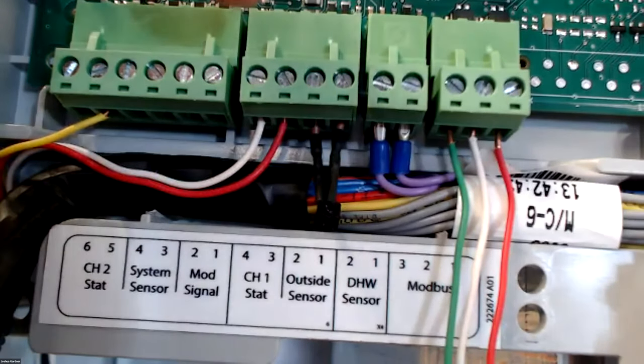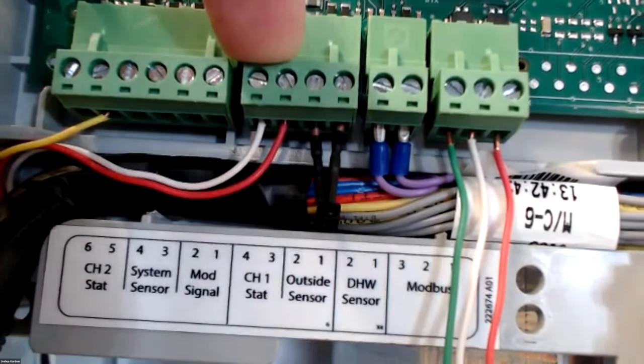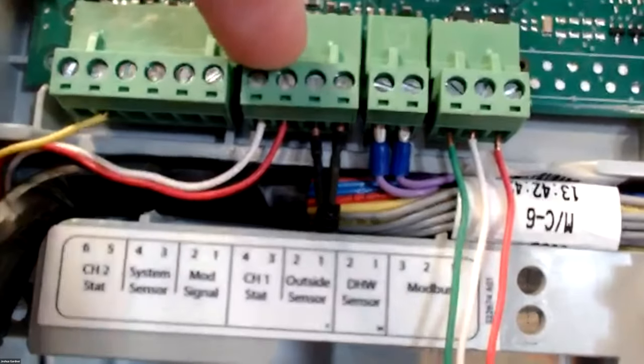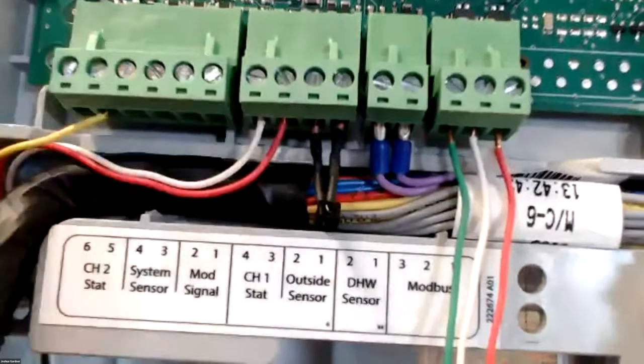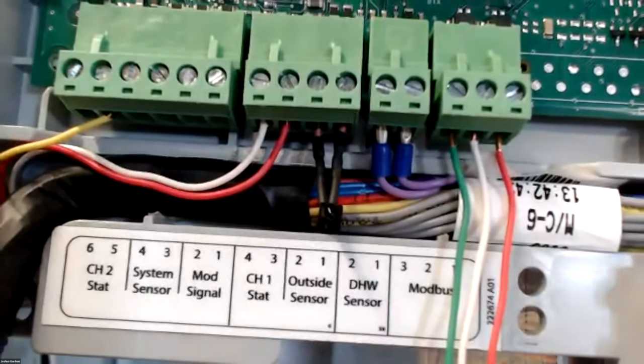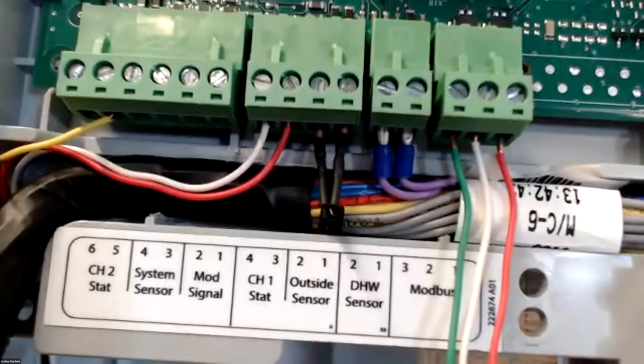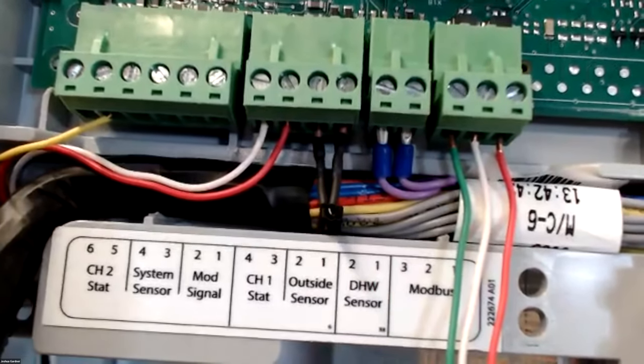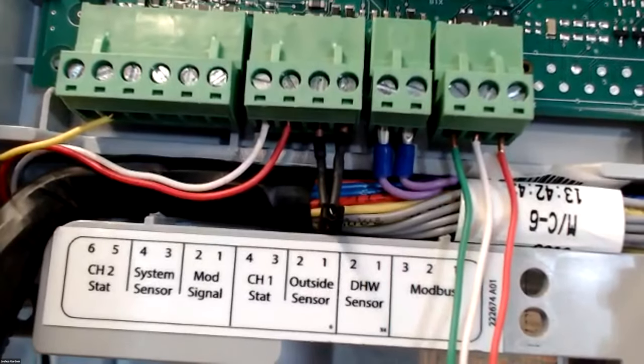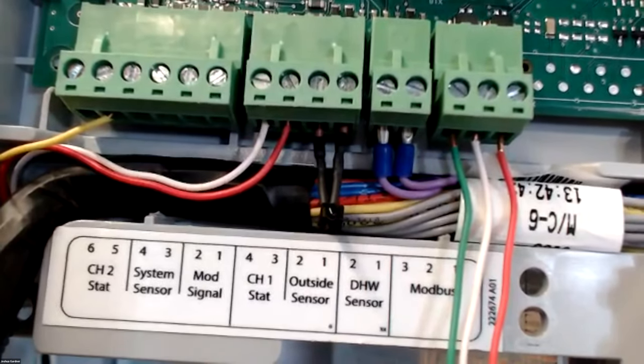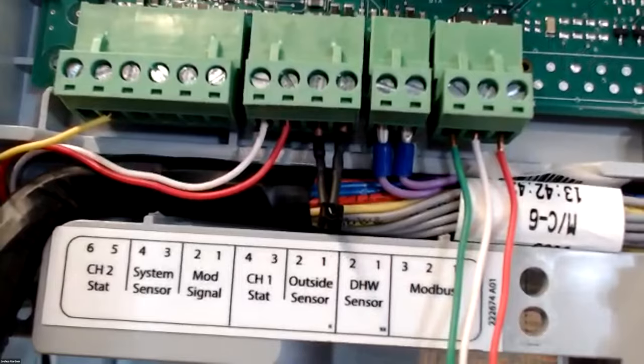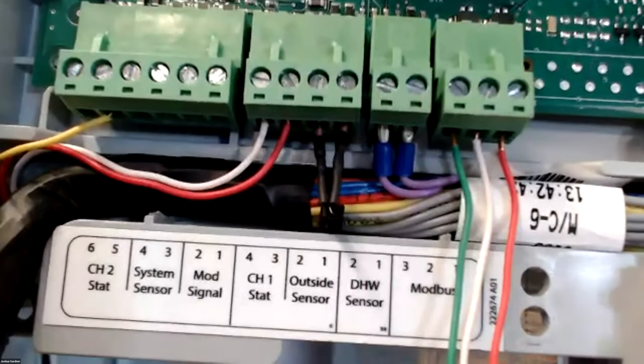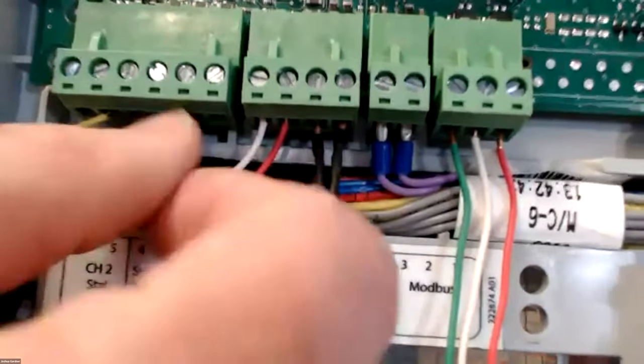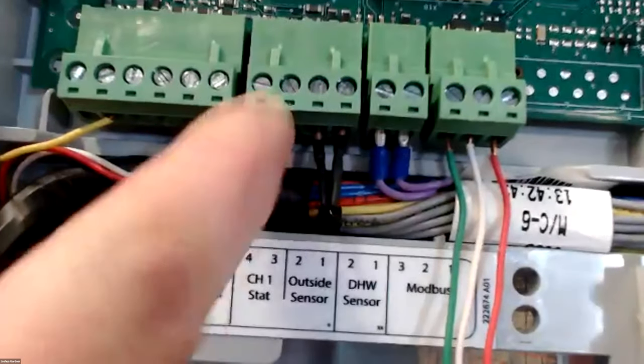I can run my thermostat right into CH1. All right, two wires, not three, don't have a common. So you've got to use that common maker, or you've got to pull in a separate transformer into that thermostat and go to RC and C and pull the jumper between RH and RC. And you could power it that way. But just note, it's only two wires, red and white, coming out for CH1.